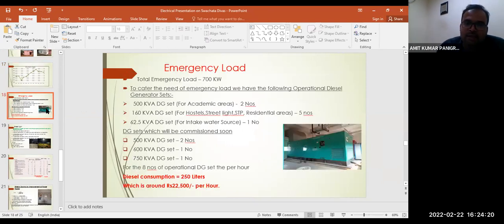There are some emergency loads in the labs, and during a power failure some of the loads need to be run continuously. To cater to the emergency load, we have different diesel generator sets at our site. The total emergency load is 700 kilowatt. The emergency load includes all in the academic area, some emergency power points which all the labs are using for emergency purposes. And for the hostel and residential area, it is only the common utilities like lift, passage light, staircase light, and our street light.